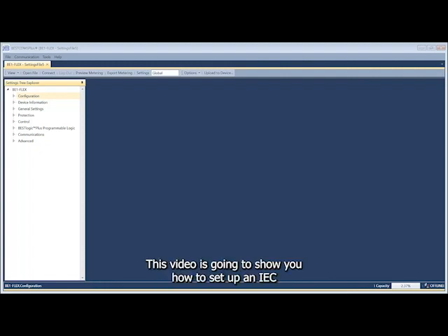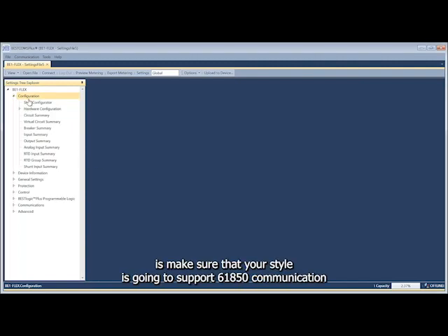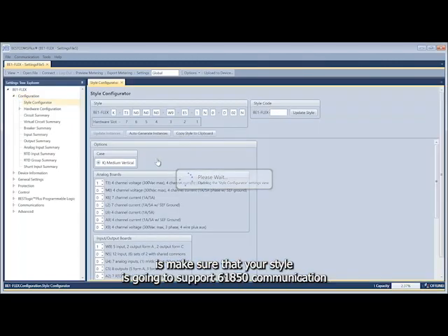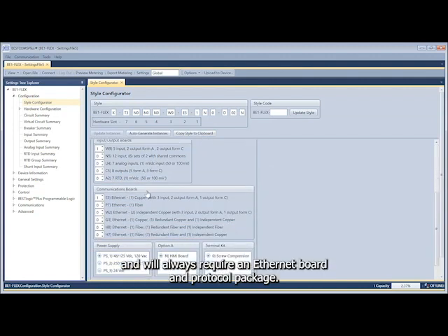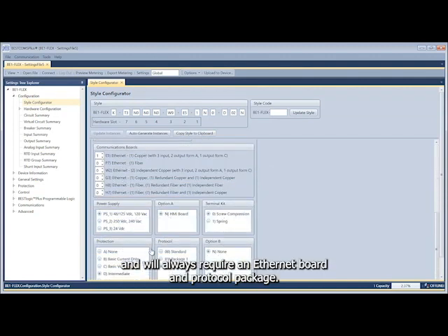This video is going to show you how to set up an IEC61850 map within the BE1-FLEX. First thing you're going to do is make sure that your style is going to support 61850 communication. It will always require an Ethernet board and protocol package 02.